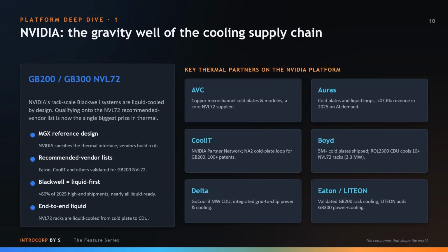Let's go deeper on NVIDIA, because it's the gravity well of this entire supply chain. The GB200 and GB300 NVL72 are rack-scale Blackwell systems that are liquid-cooled by design. Qualifying onto NVIDIA's recommended vendor list is now the single biggest prize in thermal. NVIDIA publishes the MGX reference design and specifies the thermal interface, and vendors build to it. Because Blackwell is over 80% of high-end shipments, that spec effectively sets the industry standard.